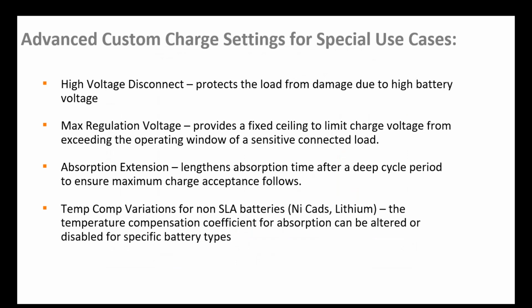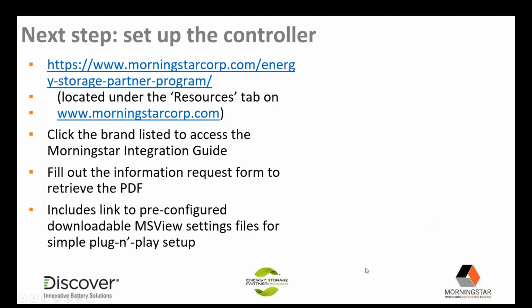Again, a few other advanced custom settings that we have available for different use cases. One is high voltage disconnect. This would be a high voltage disconnect protection on the load side. A lot of charge controllers don't have an integrated load circuit, so they can't protect the load from high voltage. But we do for DC loads. And as long as your load rating is within the rating of the controller, you can set high and low voltage disconnect threshold options.